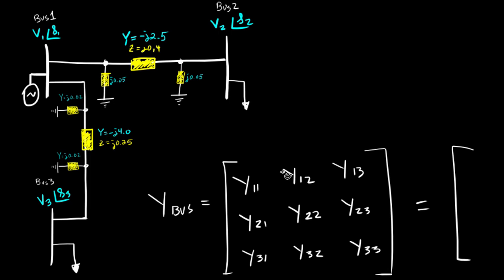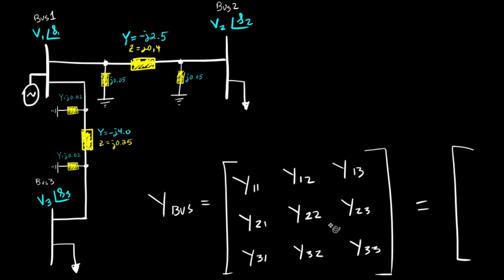One conclusion that we drew was that the diagonal elements — Y11, Y22, and Y33 — represent the admittance of a particular bus. They essentially equal the sum of all of the admittances connected to that bus. So Y11 equals the sum of admittances connected to bus 1, Y22 the sum connected to bus 2, and Y33 the sum connected to bus 3.